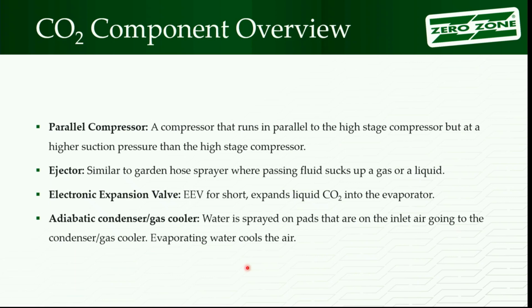So parallel compressor, remember I said that tank's running 100 pounds higher? If I can suck the gas out of that tank at 100 pounds higher with a compressor, it's going to be more efficient than my normal high stage, right? Because whenever I go through a pressure regulating valve in a suction line, it drops the efficiency of the system. You don't want to have big pressure drops in your suction line. The system's efficiency drops. So if I have a 100-pound drop, that gas is losing a lot of efficiency. I put in a parallel compressor up here, I get a more efficient system.